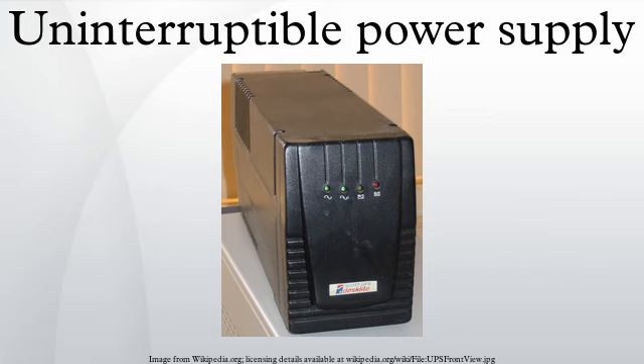Offline standby. The offline standby UPS offers only the most basic features, providing surge protection and battery backup. The protected equipment is normally connected directly to incoming utility power. When the incoming voltage falls below or rises above a predetermined level, the UPS turns on its internal DC-AC inverter circuitry, which is powered from an internal storage battery. The UPS then mechanically switches the connected equipment onto its DC-AC inverter output. The switchover time can be as long as 25 milliseconds depending on the amount of time it takes the standby UPS to detect the lost utility voltage. The UPS will be designed to power certain equipment, such as a personal computer, without any objectionable dip or brownout to the device.